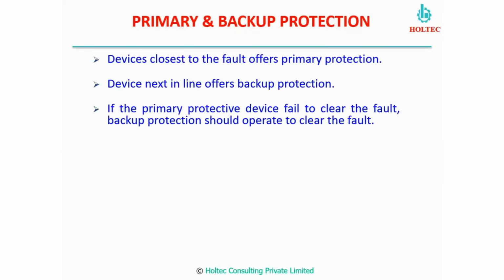There is another phenomenon which we normally discuss. It is primary protection or backup protection. What does it mean? A device closest to the fault, device means relay, offers primary protection. Any device which is very near to the fault will give you primary protection. And the device or relay next in line, after the first device, will offer you backup protection for the same fault. What does it mean? If the primary protection device fails to clear any fault, a backup device will clear the fault with a determined time delay, which is a time grading between these two devices.